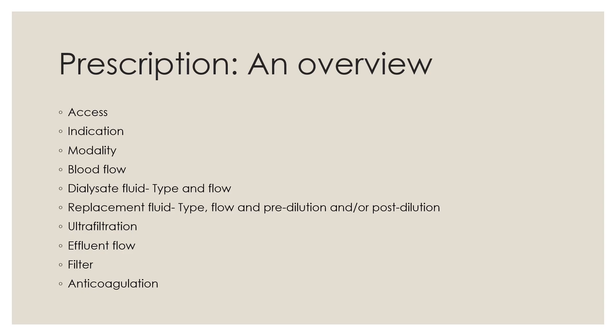While writing a CRRT prescription, physicians should provide all the relevant information based on the clinical need of the patient to implement effective and safe therapy. It includes information about access site, indication of CRRT, modality of CRRT, blood flow rate, and dialysate flow rate and type.